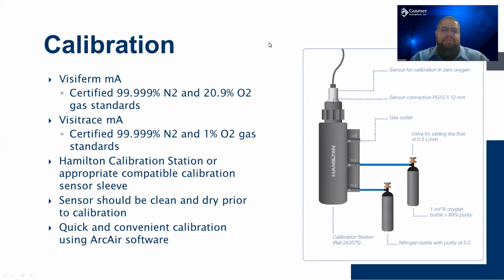When you calibrate your sensors, it's very important that your sensors are clean and dry prior to calibration. Any kind of dirt or crud on your sensor cap can affect your calibration. So you want to make sure they're clean, they're dry. You also want to make sure your sensors are at the same temperature as your calibration gas. If your sensors are still cold and your calibration gas is at room temperature, that can affect your calibration. So you want to make sure that the temperatures of the 2 are in sync.